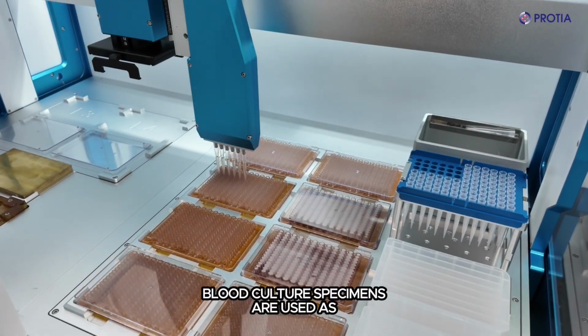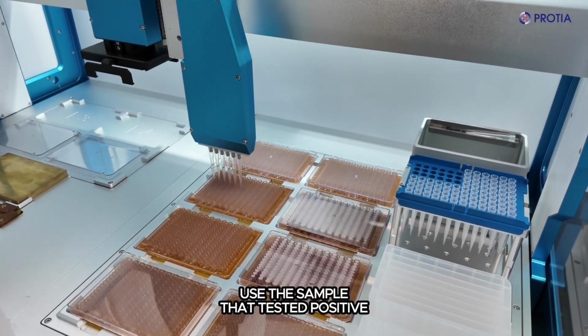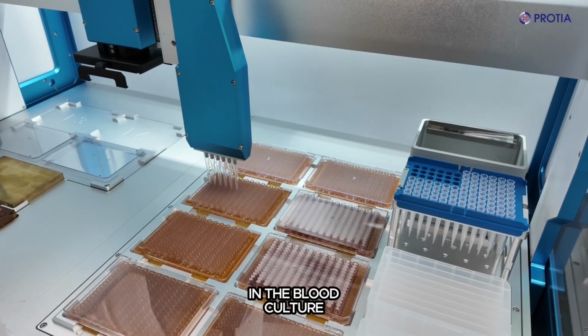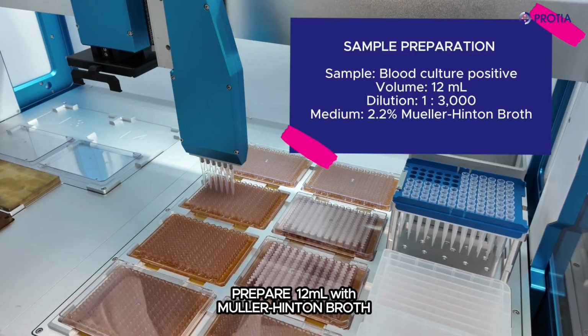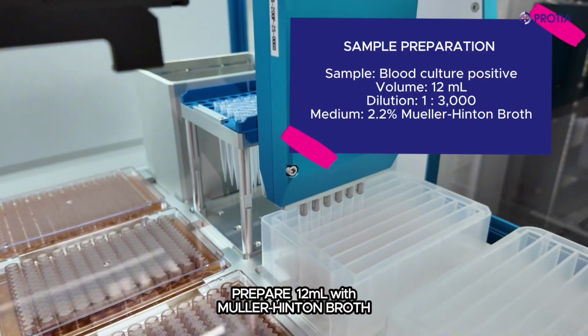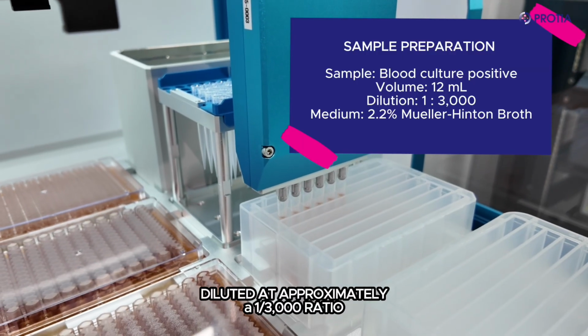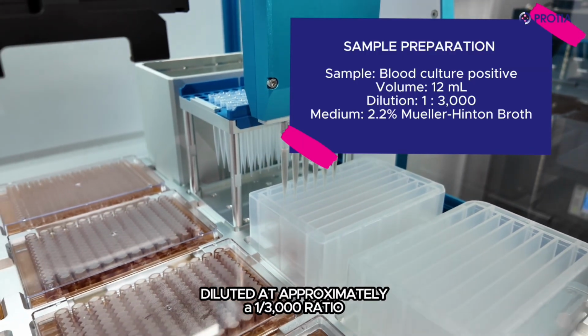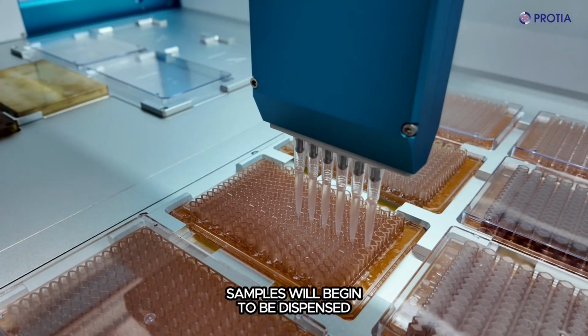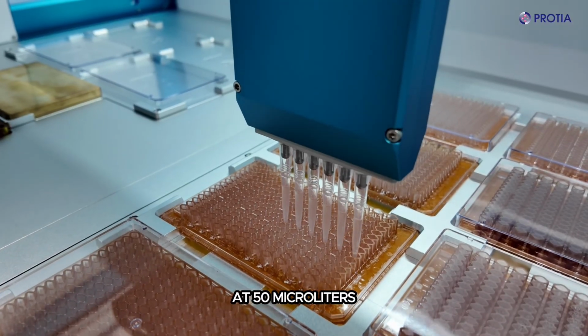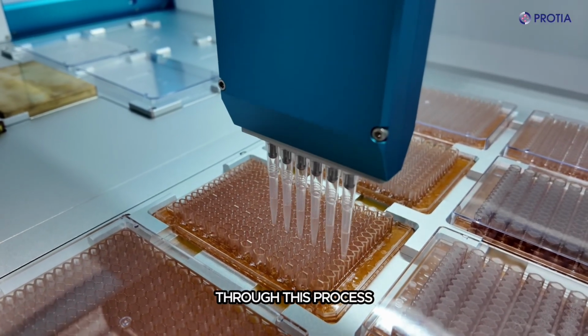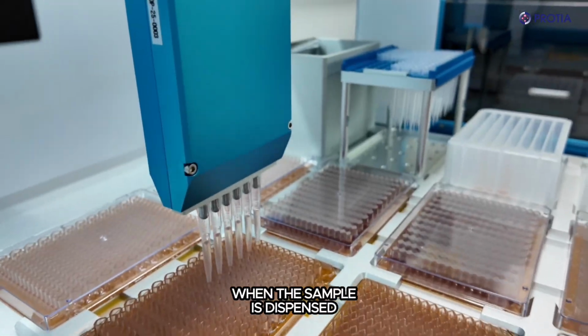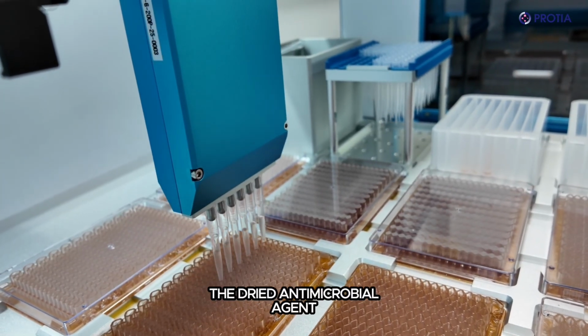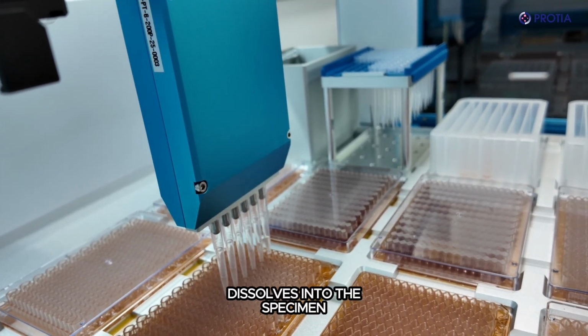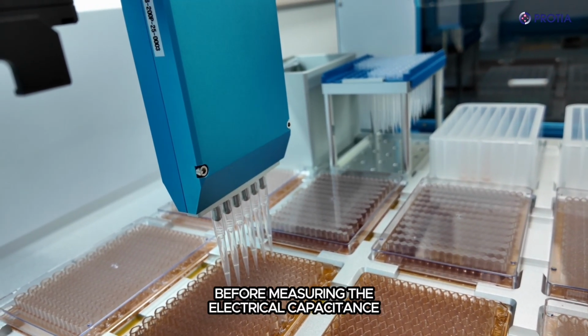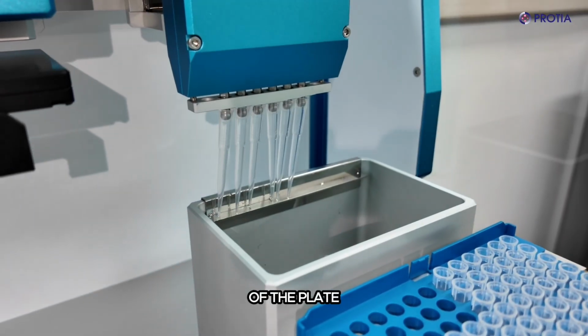Blood culture specimens are used as samples. Use the sample that tested positive in the blood culture. Prepare 12 milliliters with Mueller-Hinton broth, diluted at approximately a 1 to 3,000 ratio. Samples will begin to be dispensed at 50 microliters into each channel. Through this process, when the sample is dispensed into the wells, the dried antimicrobial agent dissolves into the specimen before measuring the electrical capacitance of the plate.